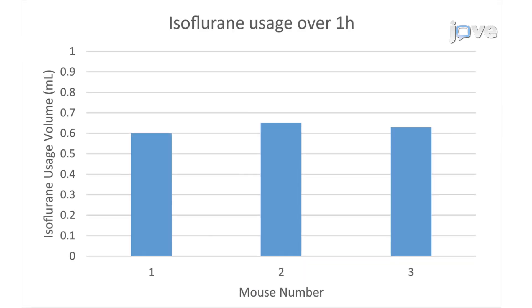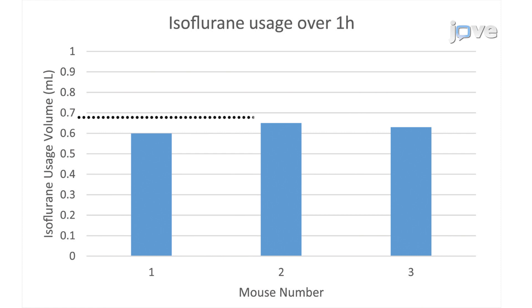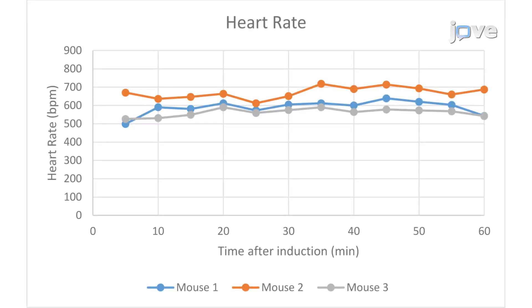This figure shows the amount of isoflurane used in milliliters for three different 6- to 7-week-old C57 Black 6 female mice over one hour of anesthesia maintenance using the digital low-flow anesthesia system. Due to the low flow rates, the low-flow syringe-driven digital vaporizer consumed less than one milliliter of isoflurane over the course of one hour. The heart rate of the three mice, measured in beats per minute using pulse oximetry at 5 to 60 minutes after induction, remained relatively stable and consistent through the maintenance period.